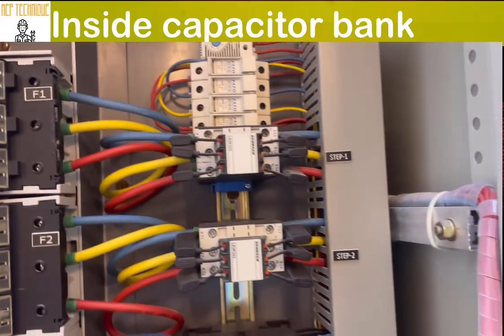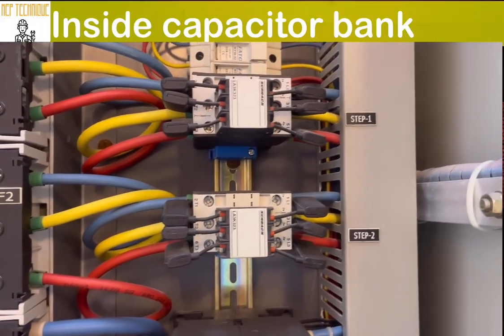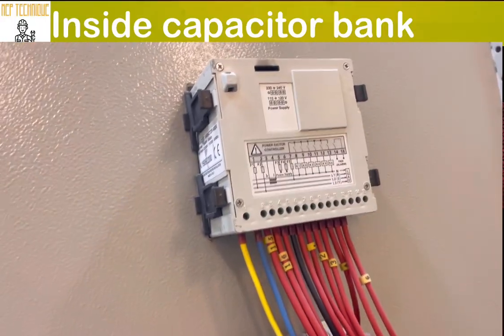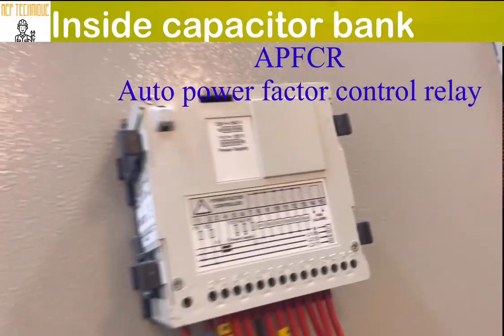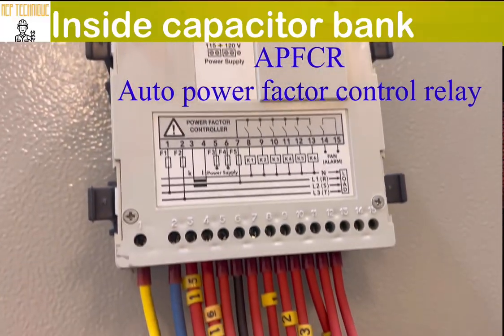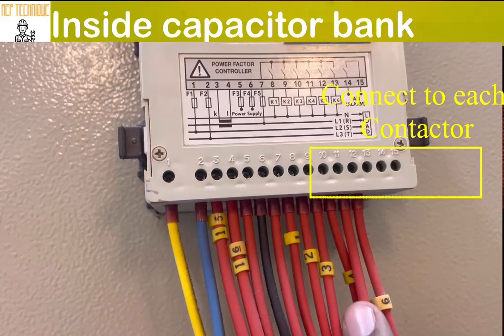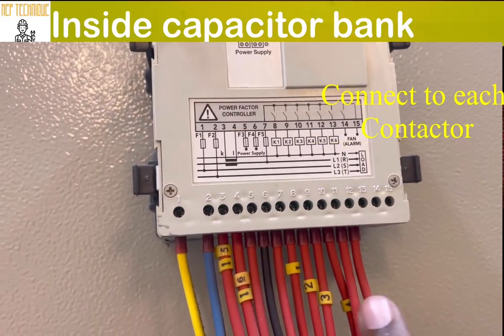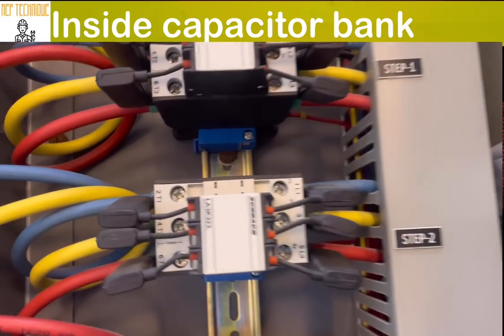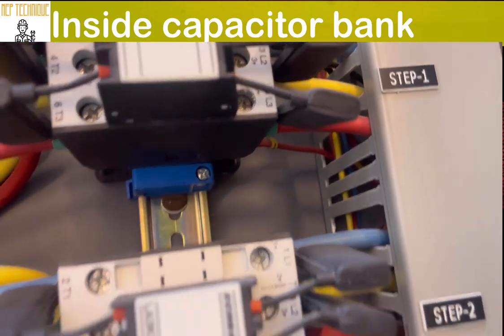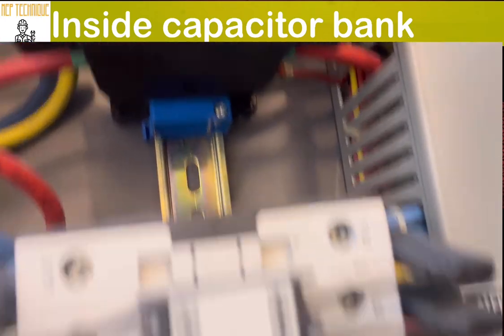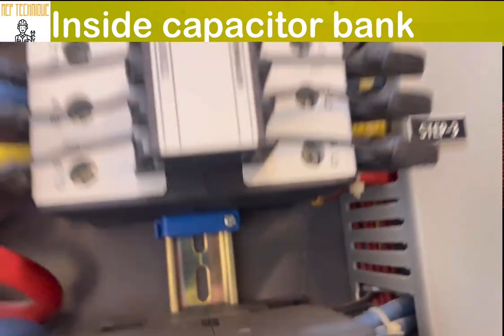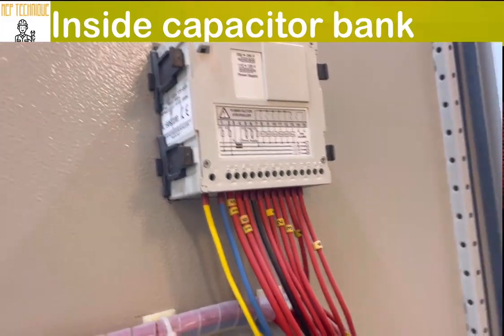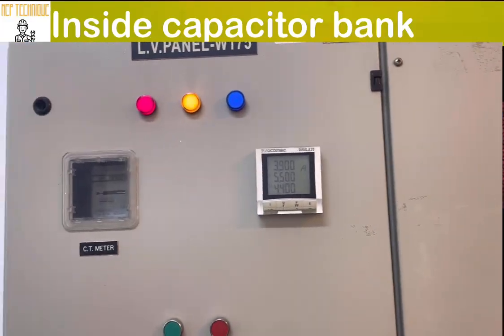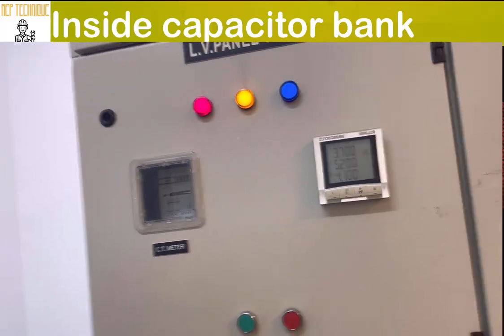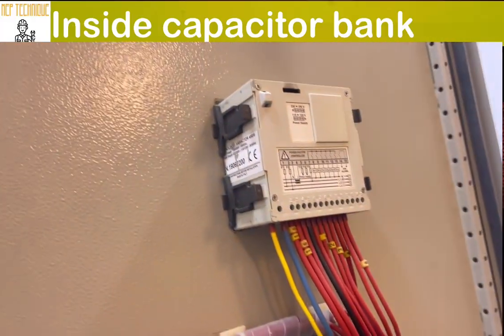Okay, so let's discuss how these contactors are connected with our auto power factor control relay. You can see there are different ferrule numbers 1, 2, 3, 4, 5, 6. These are the cables connected with the contactor 1, then 2, then 3. It depends upon the load in our MDB. When the ampere increases, more capacitor banks will be switched on. Well, how is it possible?